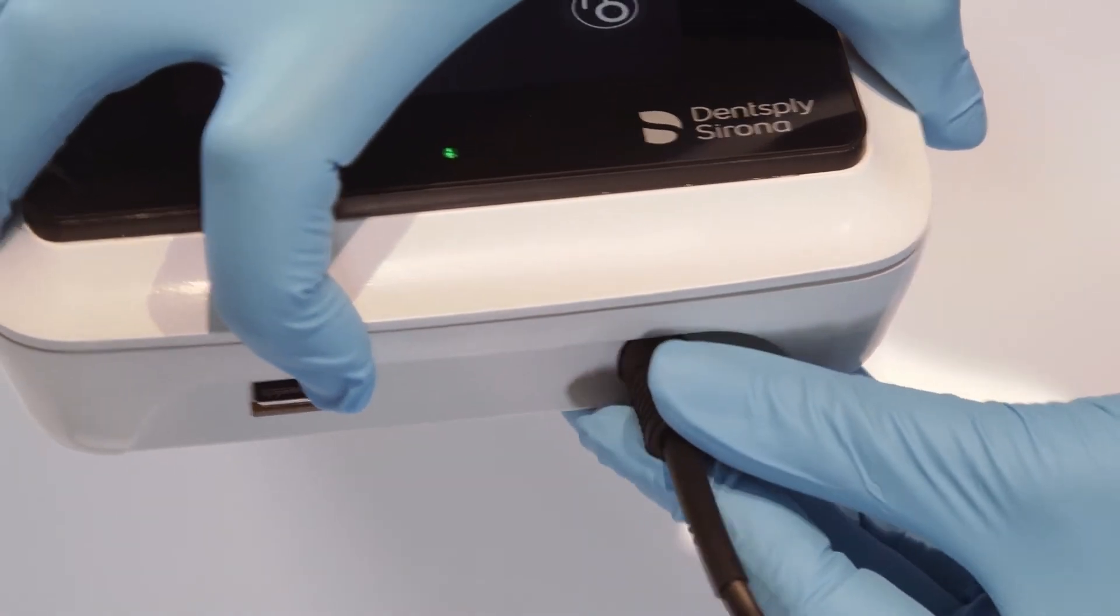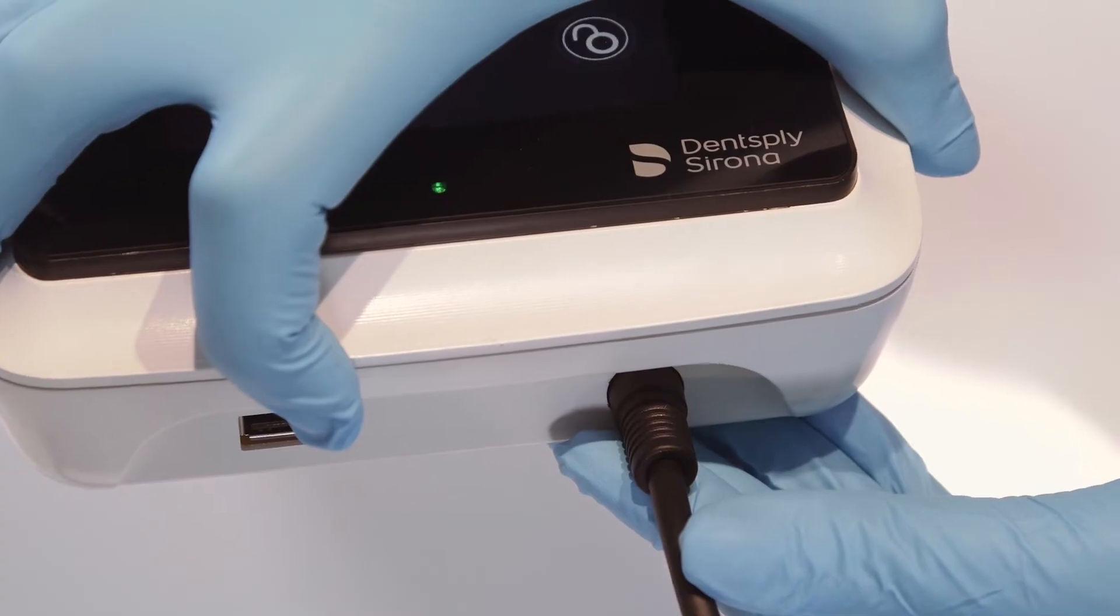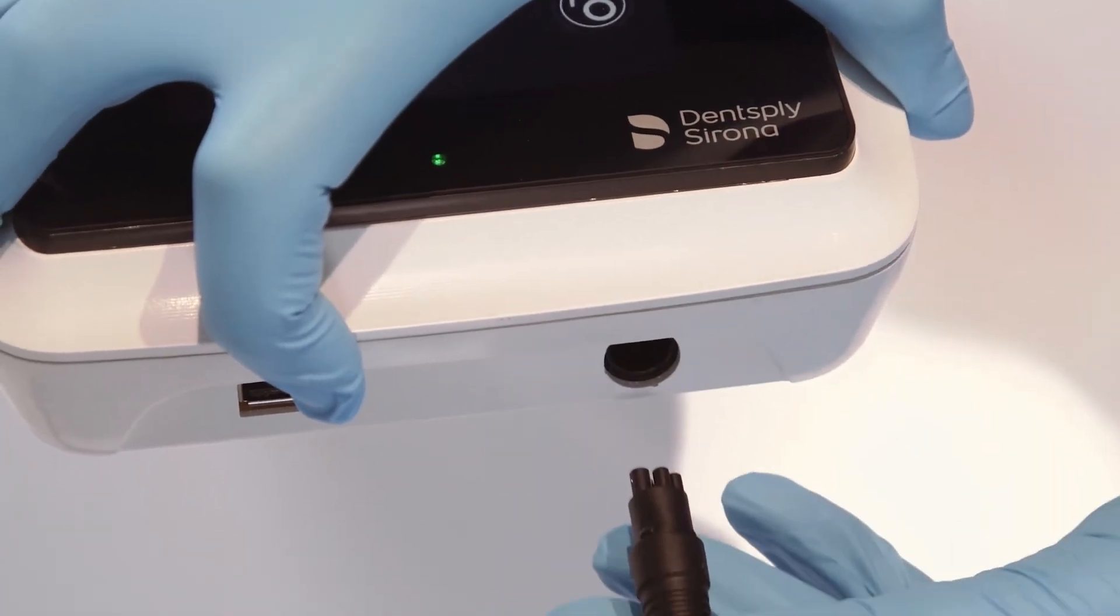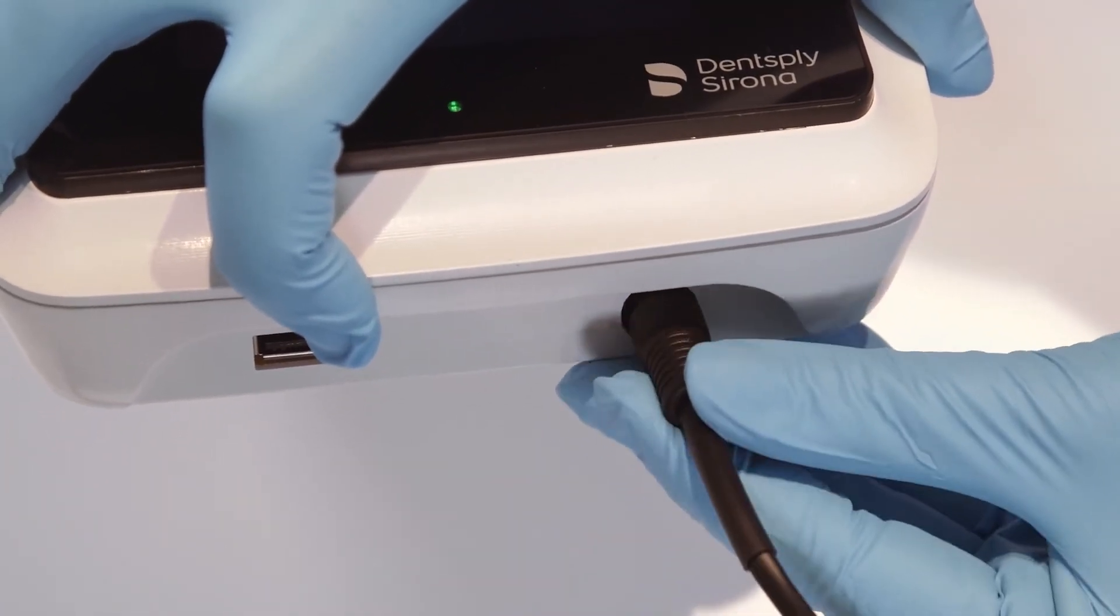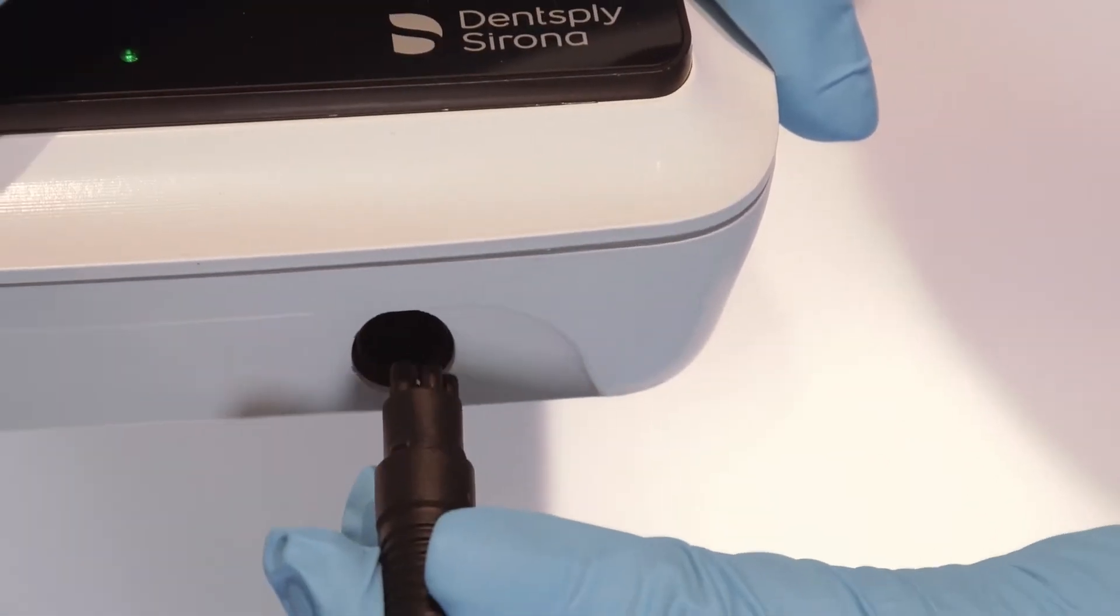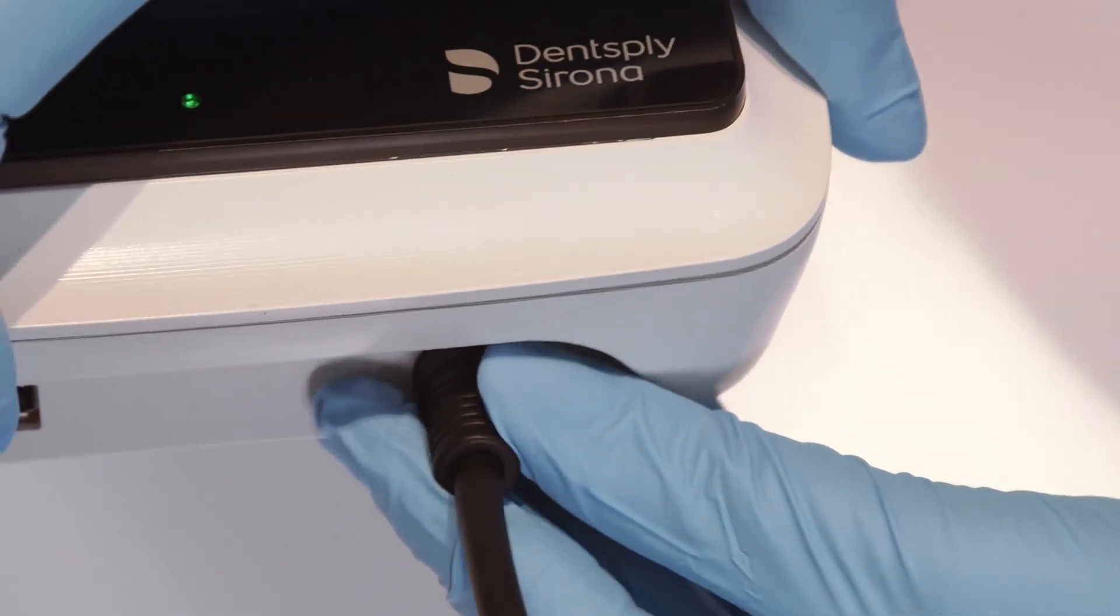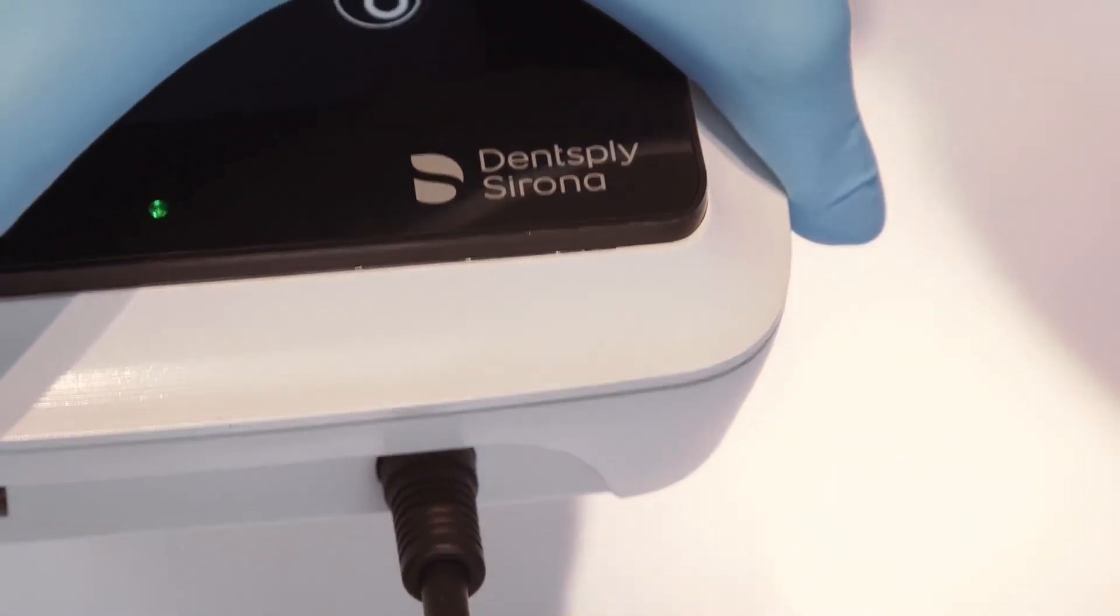To connect the featherweight handpiece cable to the Cavitron 300 series ultrasonic scaling system, insert the black handpiece cable connector into the port on the front of the Cavitron 300 series ultrasonic scaling system. If the cable connector does not seat into the system's port, gently rotate the cable connector until contacts align and then fully insert the connector.